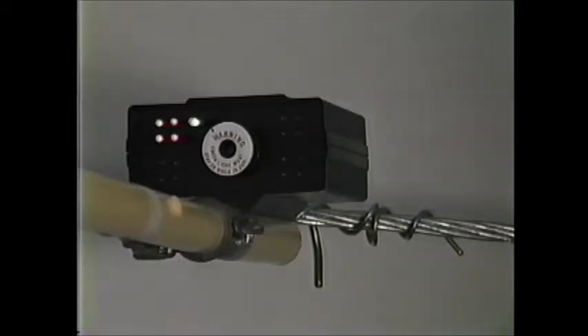This would be the display you would get on a normally operating 2,400 volt system. If connected to a 14.4 KV system or 34.5 KV system, we would know that we have more than 600 volts of induced voltage but less than full system voltage.